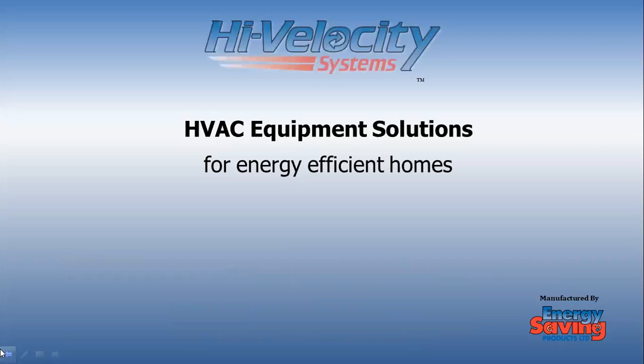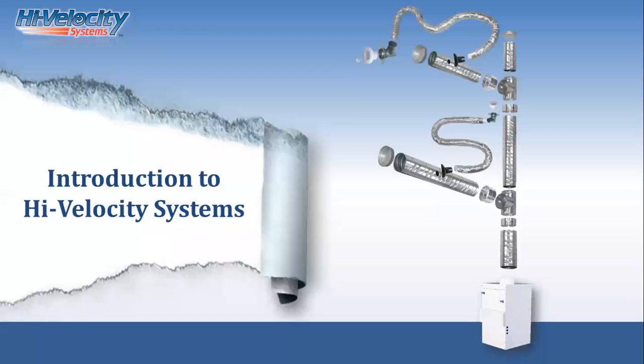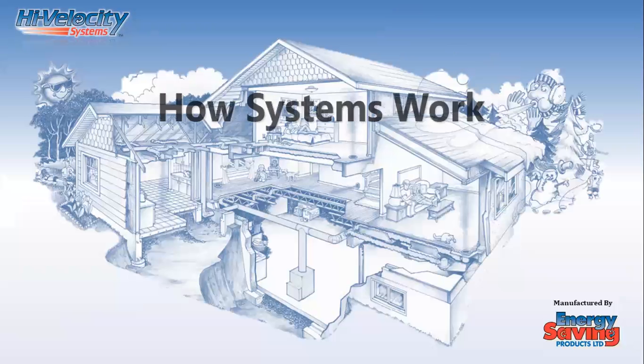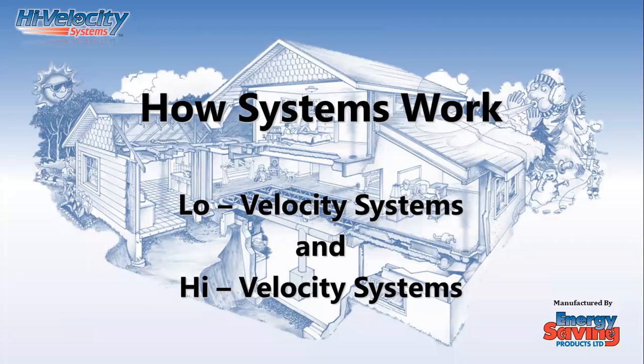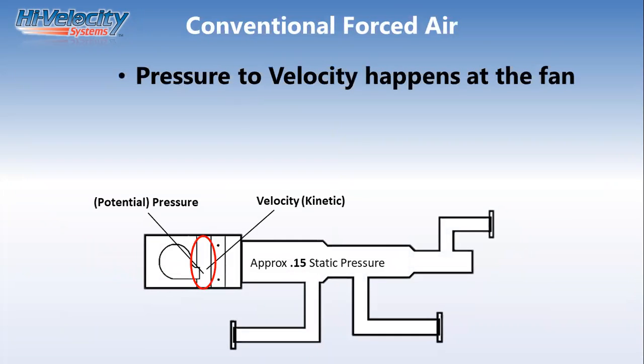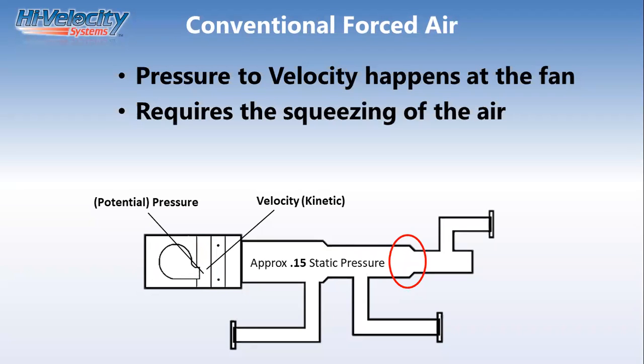Now, first off, I'm going to talk about what a high velocity system is, and a lot of it revolves around the ducting. But to understand that, a quick brief explanation on what low velocity versus high velocity means in the ducting world and the duct design world. Conventional forced air, pressure is converted to velocity right at the fan cabinet. We design on traditionally 0.1 to 0.5 inches of static pressure, which is called low velocity. It requires a proper duct design, a squeezing of the air in order to try and ensure adequate airflow at the end of the line versus what you're going to see at the beginning of the line.